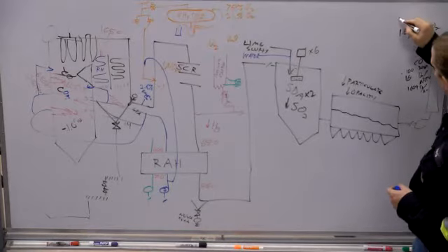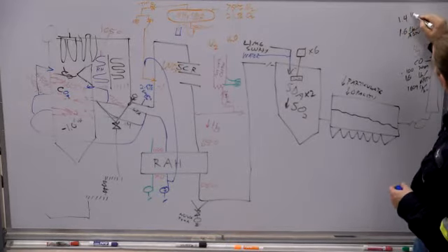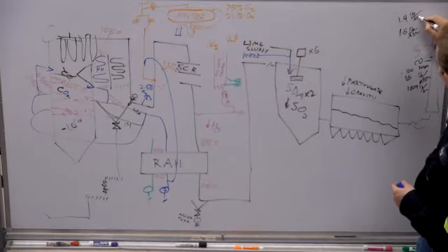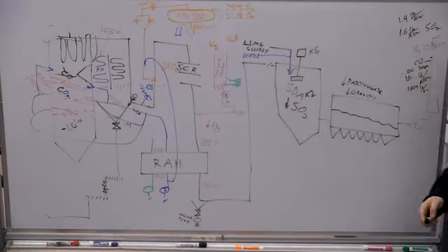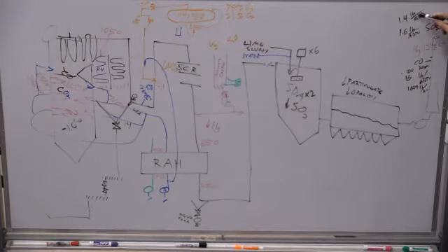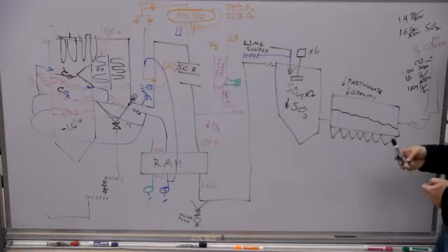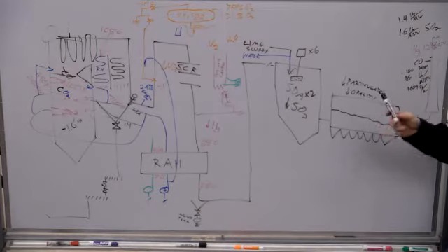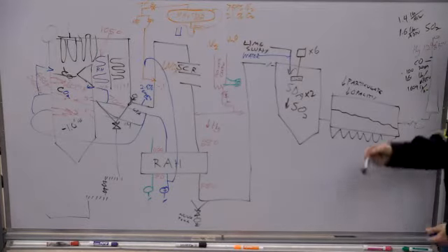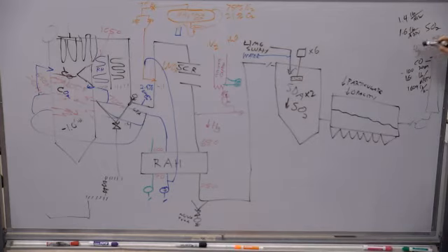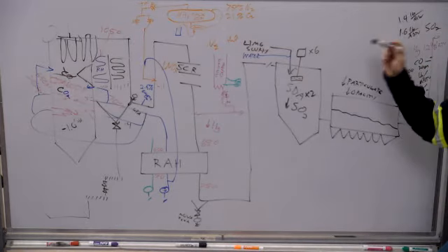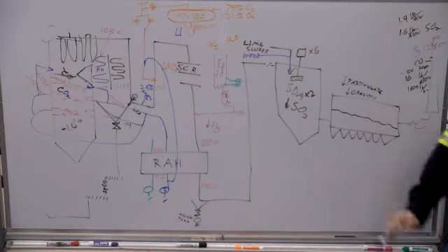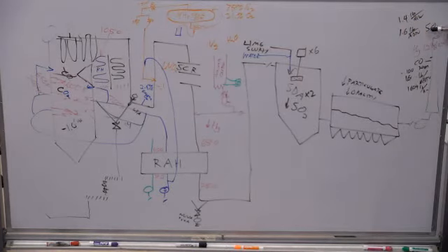And it's got a different limit. I want to say it's 1.4 pounds per megawatt. This creates a funny little conundrum, because the unit is more efficient at higher loads than at lower loads. So you use less coal, less BTUs, less coal per megawatt when we're making 700 megawatts than when we're making 400 megawatts. And because of that, this 1.4 limit is more restrictive at lower loads, and the 1.6 is more restrictive at higher loads.